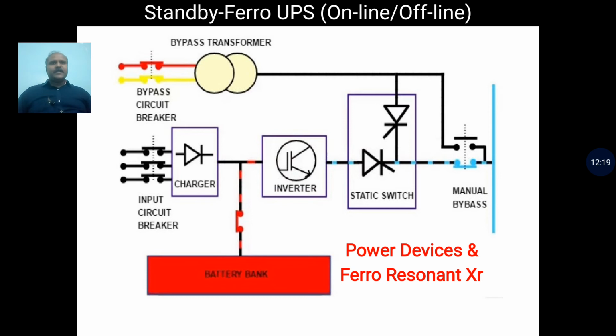When mains is present, it provides output through a special transformer having ferro resonant capacity, which provides voltage regulation as well as waveform shaping. It also provides isolation from AC transients, better than any filter available, thus providing excellent line filtering and highly reliable line isolation. This means the load experiences pure, or corrected, power through this isolation transformer. As shown in the figure, switching may be manual or automation based. This block diagram is a schematic used for the purpose of understanding.